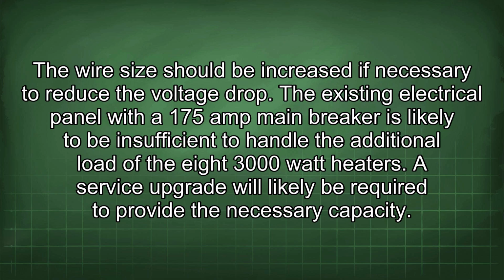The existing electrical panel with a 175 amp main breaker is likely to be insufficient to handle the additional load of the 8 3000 watt heaters. A service upgrade will likely be required to provide the necessary capacity.